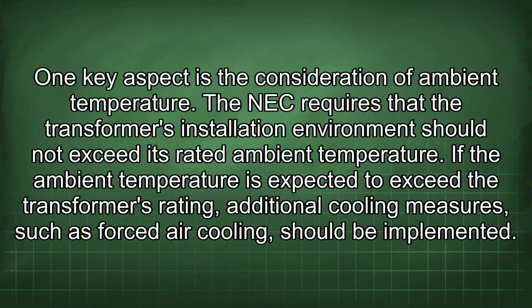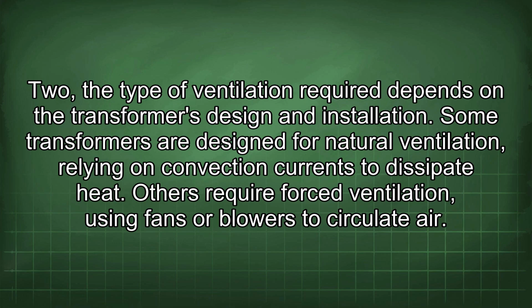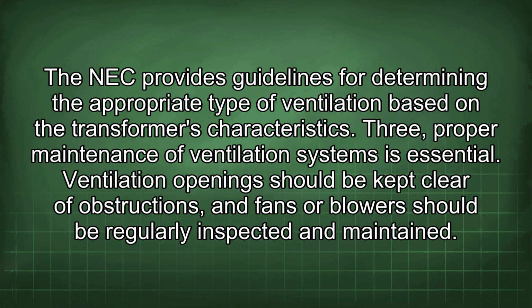1. One key aspect is the consideration of ambient temperature. The NEC requires that the transformer's installation environment should not exceed its rated ambient temperature. If the ambient temperature is expected to exceed the transformer's rating, additional cooling measures, such as forced air cooling, should be implemented. 2. The type of ventilation required depends on the transformer's design and installation. Some transformers are designed for natural ventilation, relying on convection currents to dissipate heat. Others require forced ventilation using fans or blowers to circulate air. The NEC provides guidelines for determining the appropriate type of ventilation based on the transformer's characteristics.